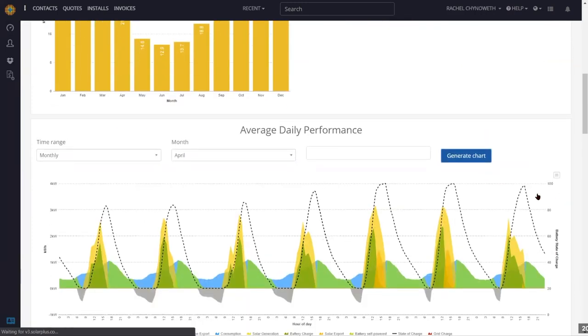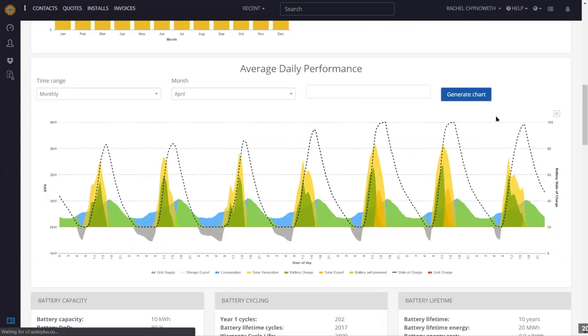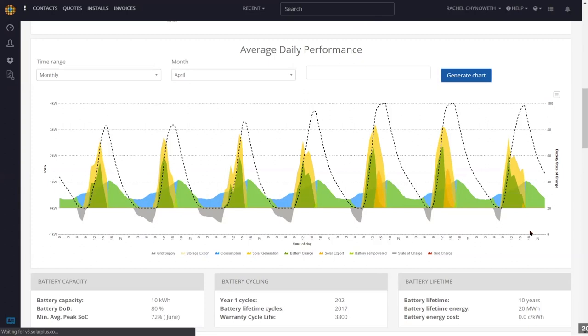This is one of my favourite graphs in Solar Plus for assessing whether you've matched your solar and battery design in line with customer expectations. This is looking at the worst time of year — around the winter solstice. This is sort of the most grid-dependent this customer will have throughout the year. Grid power usage is shown in gray, and this black line is estimated battery state of charge — I had it cycling daily at 80%. That gives you a really good idea of whether you've sized your solar and batteries correctly.